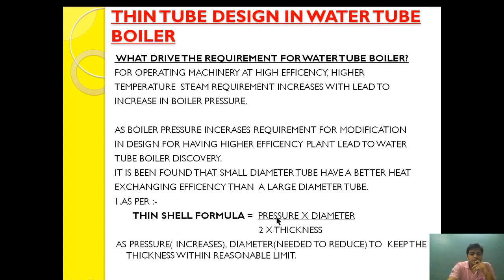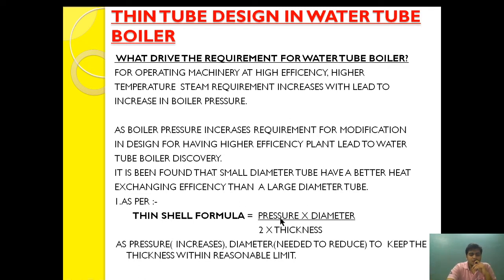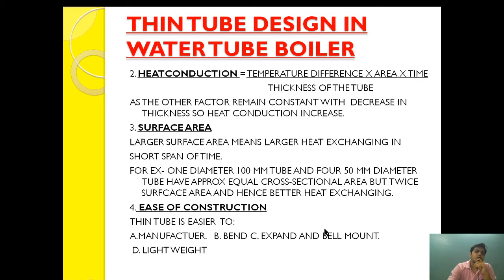According to the thin shell formula: Stress = Pressure × Diameter / (2 × Thickness). If pressure is increasing, we have to decrease the diameter to keep the thickness within a reasonable limit. If pressure increases and we also increase the diameter, we would have to increase the thickness too — which would ultimately reduce heat exchanging efficiency. So as pressure increases, we reduce the diameter so that thickness can be kept within a manageable and manufacturable limit.